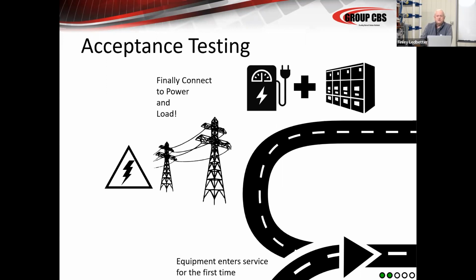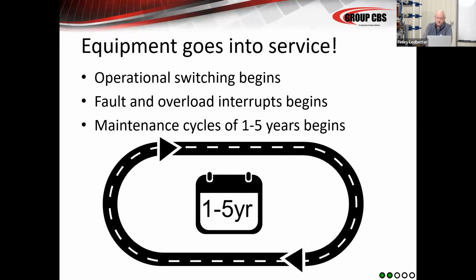When that energy is passed through the breaker, it's actually called work. So you start to do equipment work and that enters service. And when that happens, you start this first 5-year maintenance cycle. So operational switching begins. It starts to watch for faults and overloads.